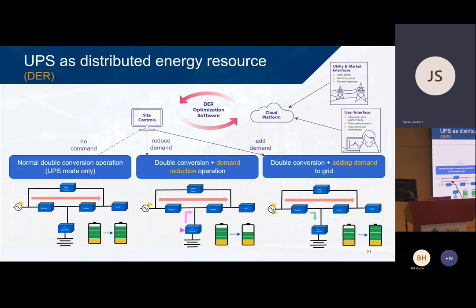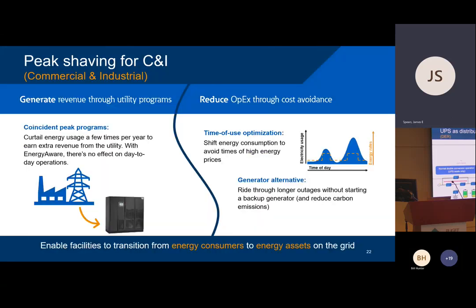Let's say I have a hospital campus with 9 buildings, and in those buildings a total of 25 UPS systems, all different sizes with different amounts of battery capacity available. We deploy a company that specializes in this, providing what's known as aggregation software. It manages all 25 UPS systems, and to the grid operator we look like one large distributed energy resource they can pull from if necessary to help balance the grid.